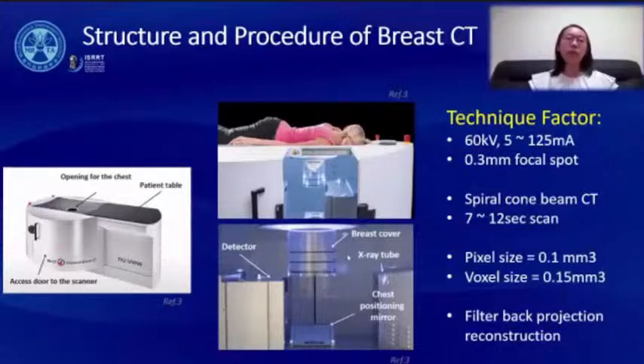Okay, let's have some concepts for the structure and procedure of breast CT first. This is the picture of the breast CT scanner, and there is a cone on the top of the scanner. The patient is prone and the breast is put in the breast cover. The tube and the detector are under the table and rotate around the single breast and get the image. So we are using a 60 kV, 5 to 125 mA cone beam CT, and the scan time is 7 to 12 seconds for a single breast exam, and the pixel size is 0.1 mm, while it is 0.15 mm in voxel. A filtered back projection reconstruction method is used.